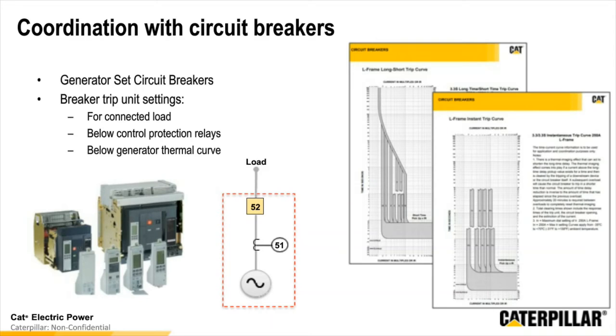The settings and the different information that's available should be available to you from your manufacturer. Caterpillar has spec sheets that you can work with your Cat dealer on, for all the breakers that we provide, so that you can get the data that you need for these coordination studies based on the specification sheets, so that you can understand what the requirements are and how to size the breaker and how to set the breaker within your system.